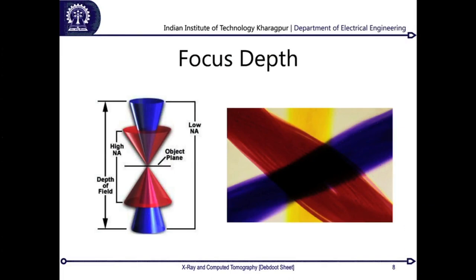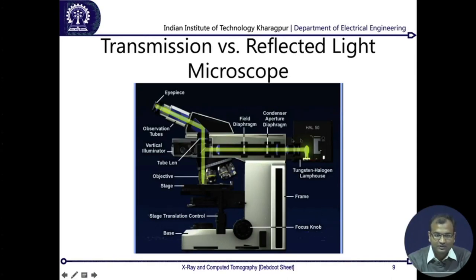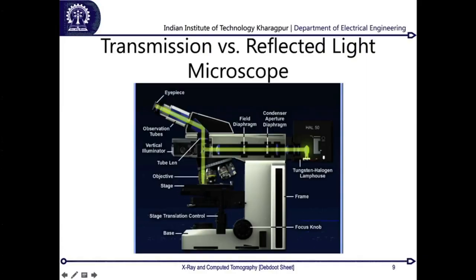Another microscope variant is the reflected light microscope. In a transmission microscope, light from the light box passes up through the sample to the objective. In a reflected light microscope, the light box illuminates through the objective itself — useful for opaque objects where transmitted light cannot pass. A beam splitter inside the microscope separates the illumination path from the imaging path, so the same objective is used for both illumination and collecting the reflected light, without blinding the viewer.